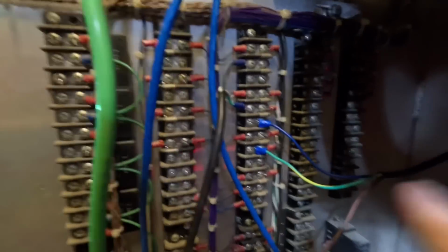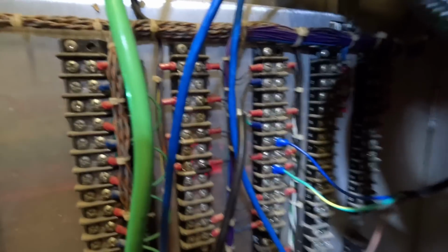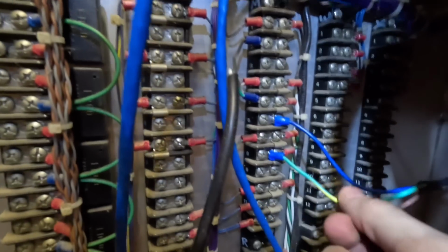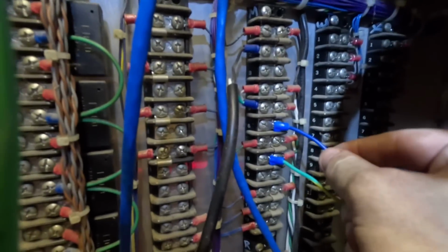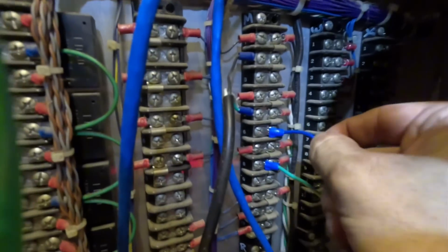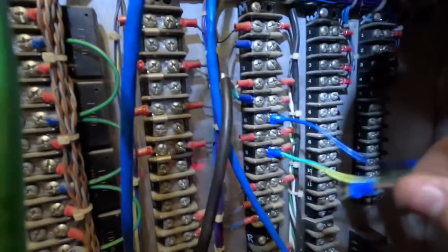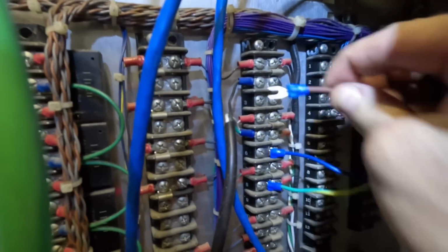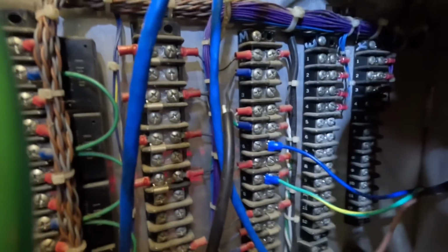Also, anytime you're trying to wire up something while it is currently hot, meaning there's 120 volts on the top side right here, you want to go ahead and land your ground and your neutral first. If you land your hot first, you will energize your neutral, meaning you just have more cables to deal with that are going to be hot and that can shock you. If you do it this way, it's only going to be the power that's going to be hot at any given time. So, a little tip for you guys.